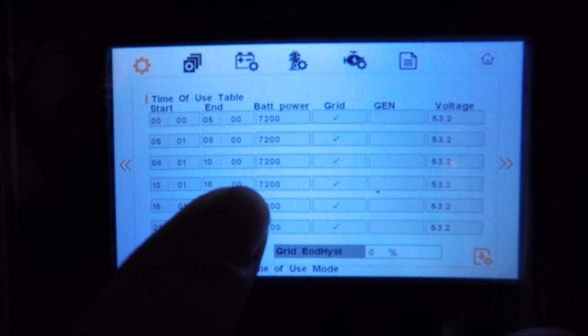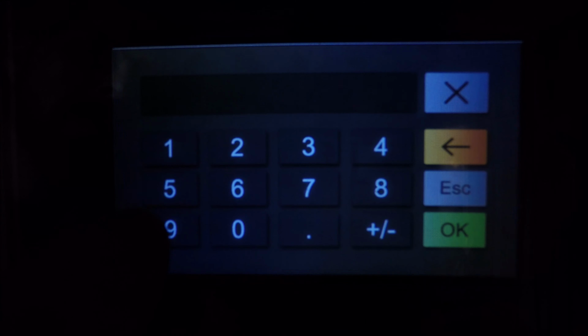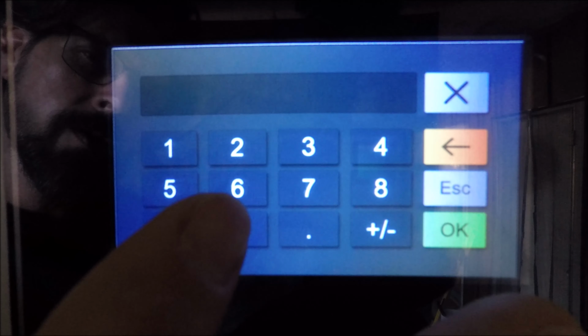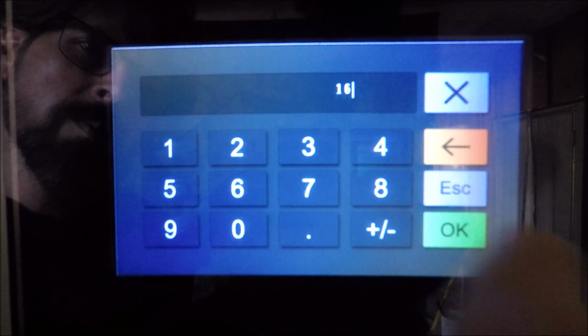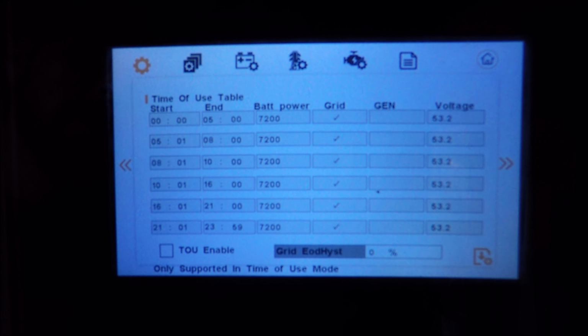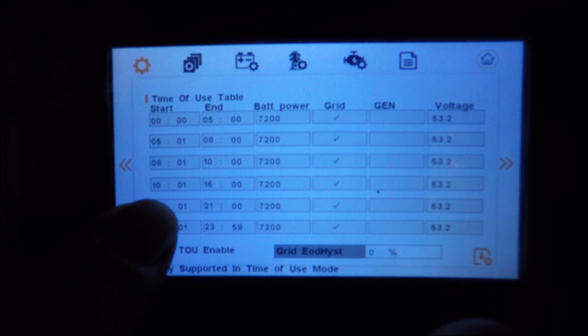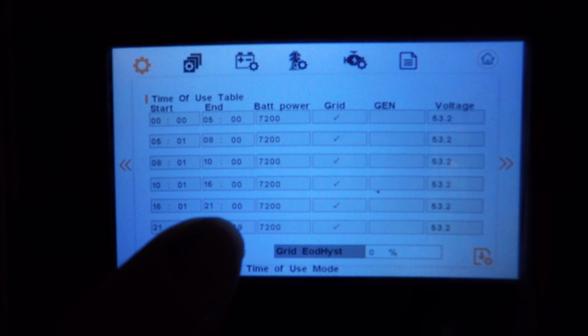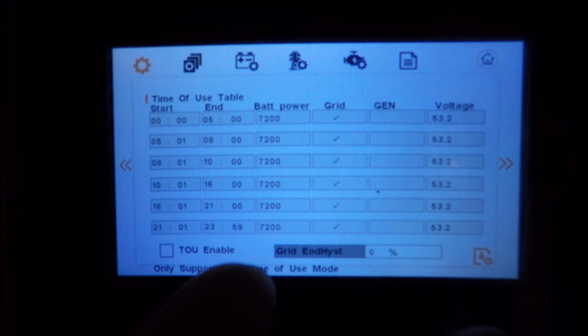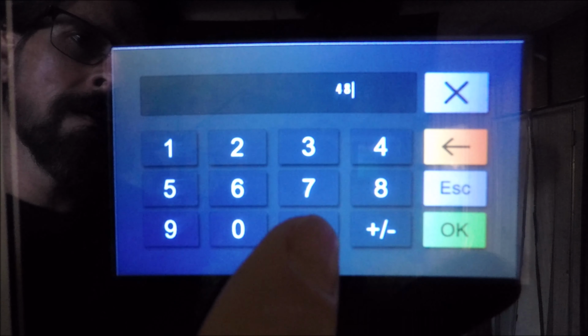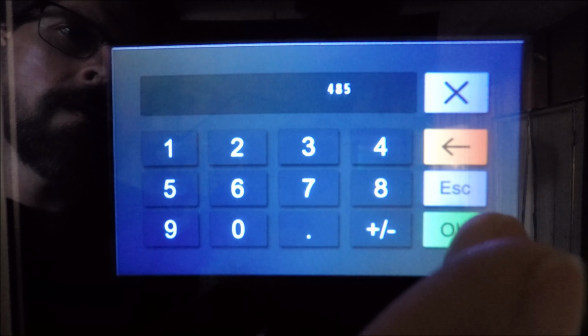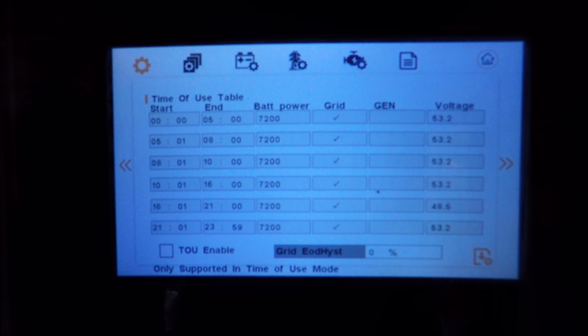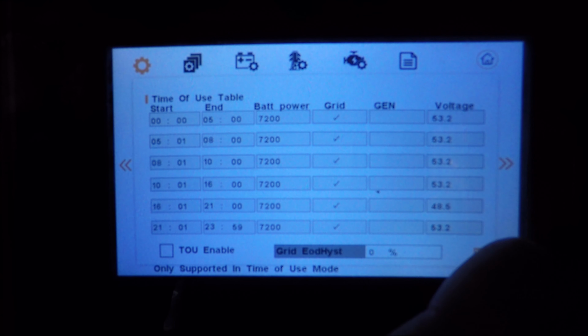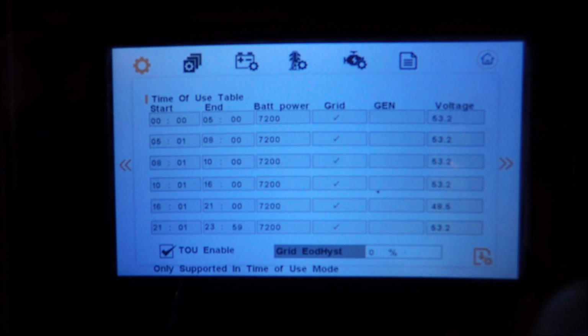That would be 4 p.m. And we're going to change the 15 here, which is currently 3 p.m., to 16, which makes that 4 p.m. 2100 hours is 9 p.m. So between 4 p.m. and 9 p.m., we're going to allow the batteries to be discharged to 48.5 volts. This will let it discharge 30 or 40%. We're going to hit save, and we're going to enable time of use.